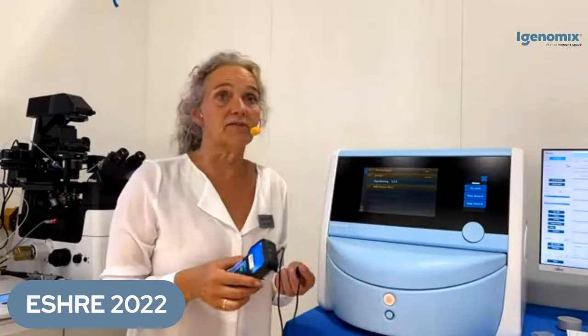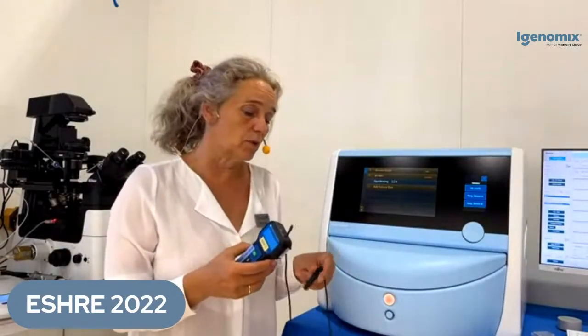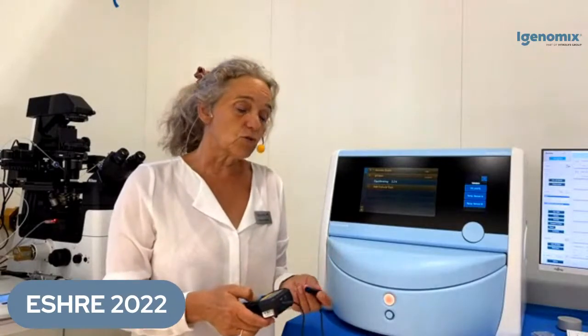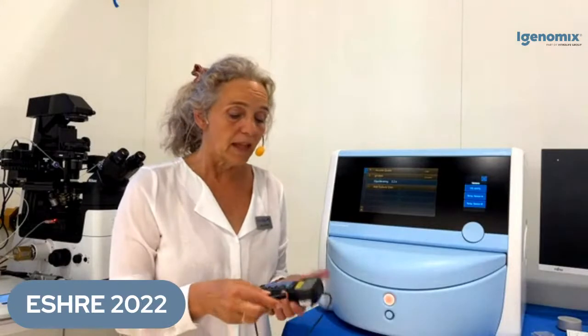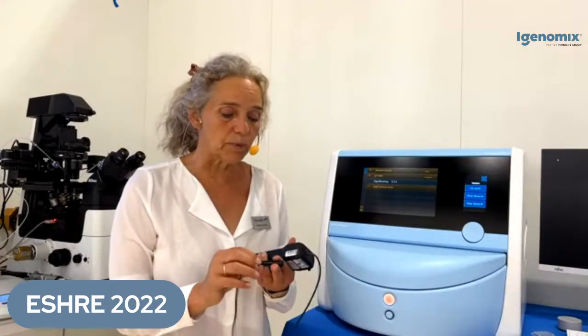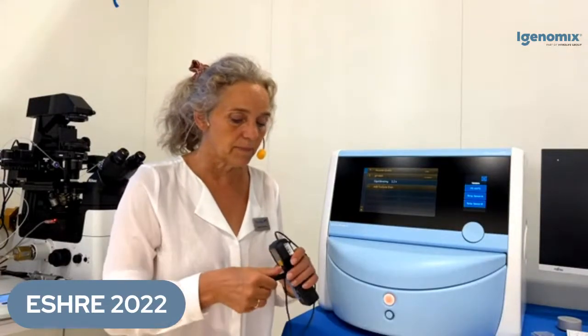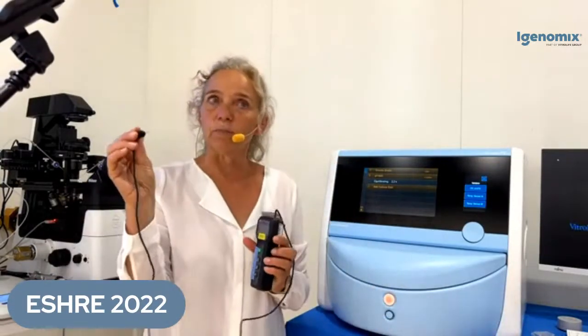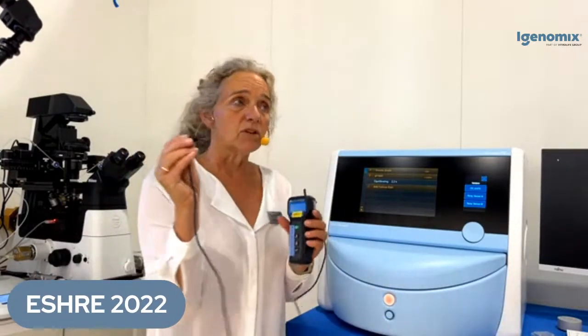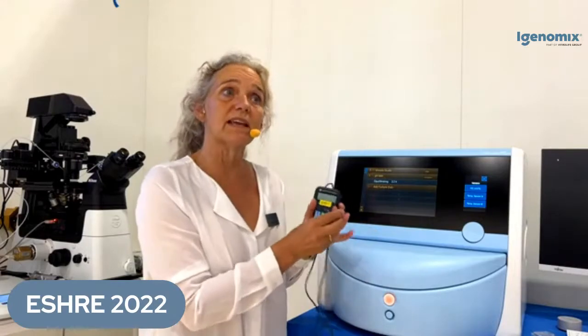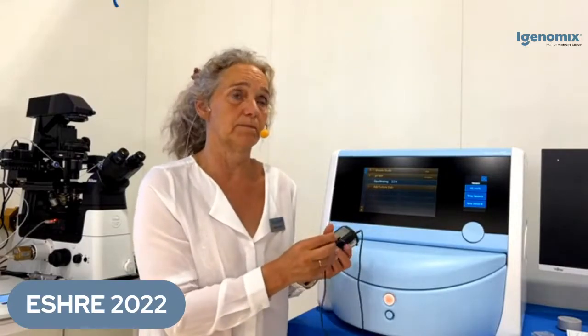When you perform calibration and validation of the temperature, Vitrolife recommends you to use a high precision thermometer, and the size or diameter of the probe should be 1 millimeter, because it should fit directly into the temperature channel when you do your validation to make an accurate measurement.